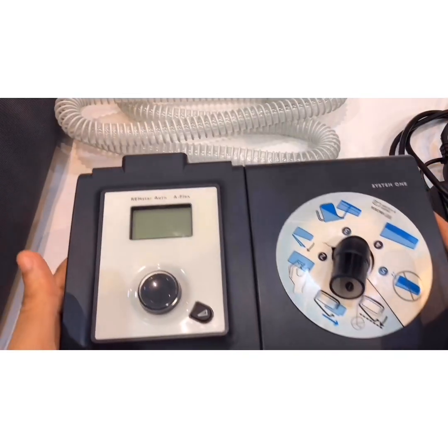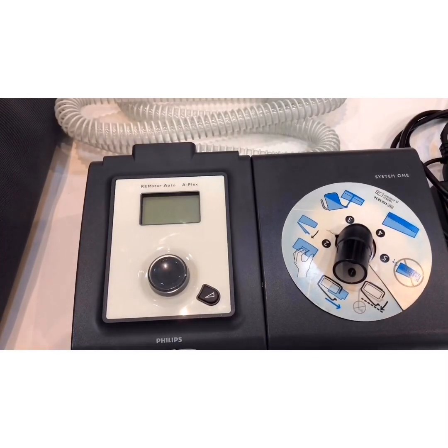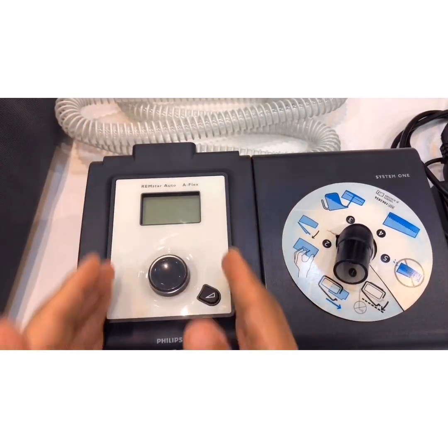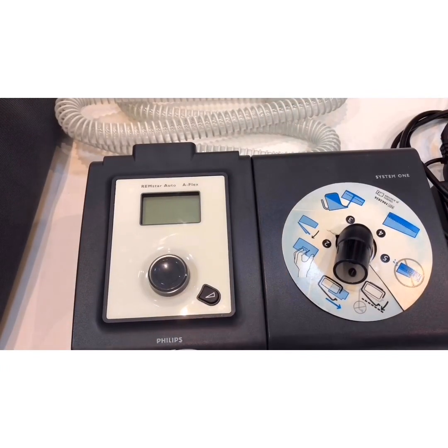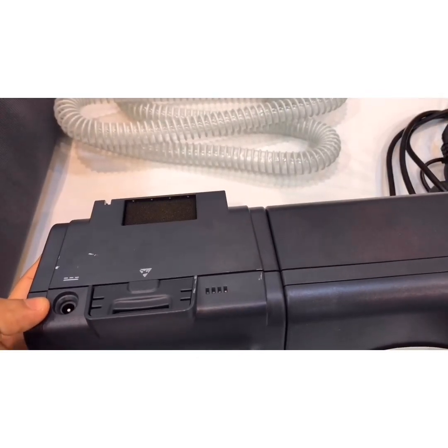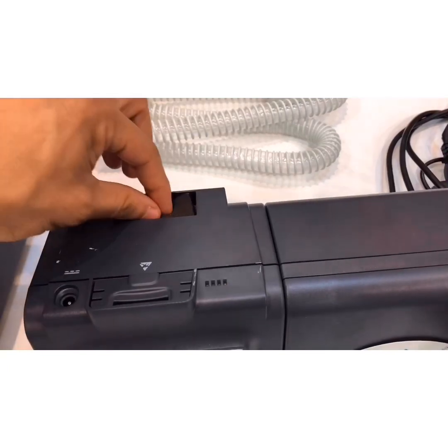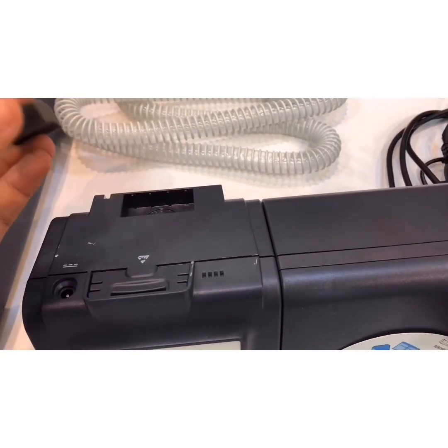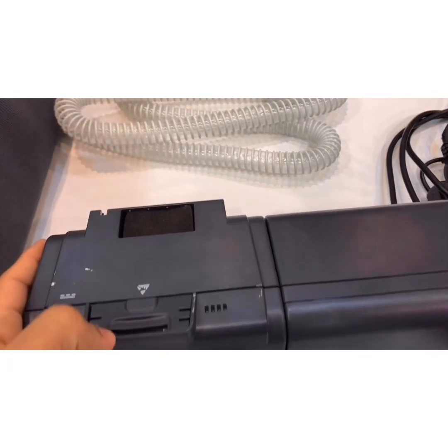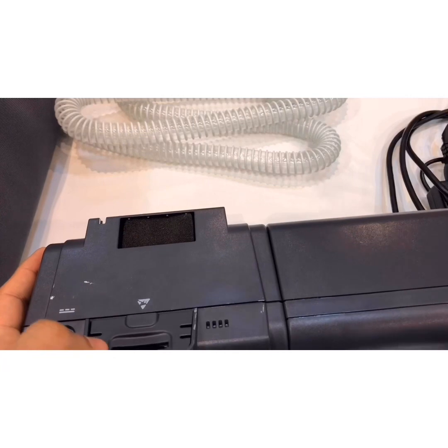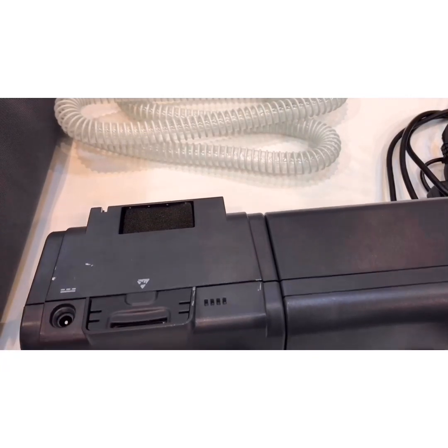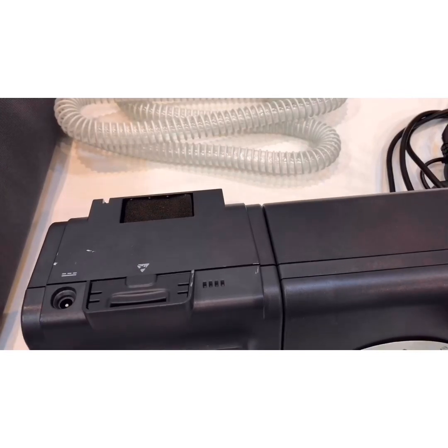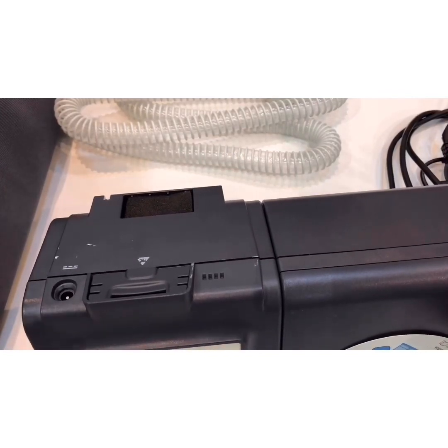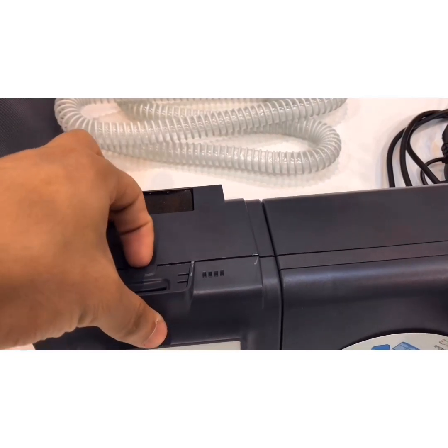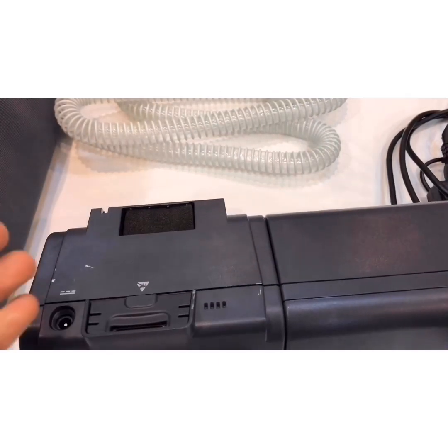So let's go with the external part of the device. This is only the delivery unit, and this is an optional humidification system. From the back, we have the inlet for the cord, and this is the reusable filter, which should be cleaned from time to time. Here we have the SD card inlet. However, we don't have the SD card here. If it is available, it can be used if we want to see a specific event on a specific night for a patient, let's say. And this is the cover for the SD card. However, it is not mandatory to use.